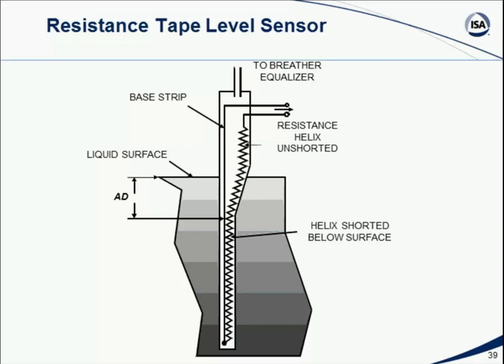Now, if we submerge this tape into a fluid, what's going to happen is that as the fluid level goes up and up and up, we submerge the tape by a certain amount. Once the tape has been submerged by a certain amount, the pressure generated by that amount of fluid will cause the tape to collapse, causing the two conductors to touch and short out. So if the tank's totally empty, then this resistive strip is not touching anywhere, and I have the maximum resistance. As the fluid level in the tank goes up and up and up, more and more of this tape is crushed or pressed in, and the resistive part of it touches and is shorted out, and so the resistance drops lower and lower and lower.